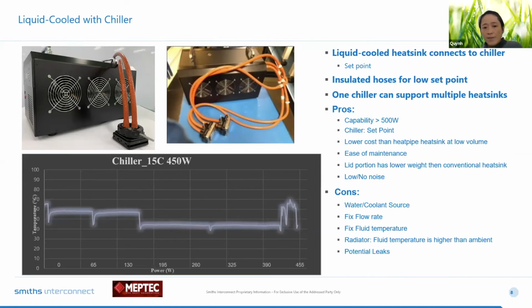The only thing is that if you use it with the water line in the lab or the radiator, then you cannot change the temperature or the flow rate of the fluid. Therefore, if you need to manipulate the temperature, use it with the chiller. But when you use liquid cooling, we need to pay attention to leakage.